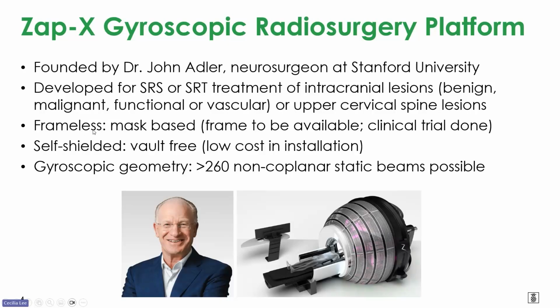So some unique aspects of the machine: one is that it is self-shielded. So if you want to install this machine in a new vault or new building, your installation cost is going to be lower. And another unique aspect is that the machine has a gyroscopic geometry, which allows multiple non-coplanar static beams, and some beams that a conventional LINAC cannot reach.